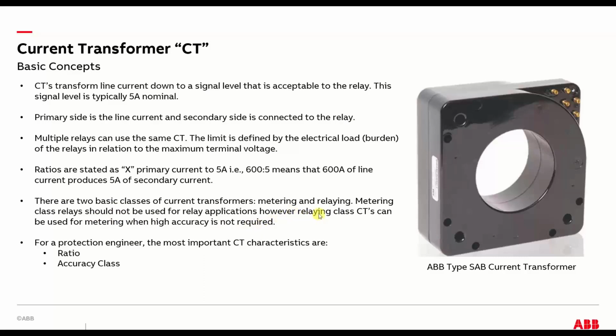They're not designed for that. They're designed to be accurate, but they're not designed to have a large range on them. So when you do a relaying application, you're going to select a relaying class CT. Now in the inverse, a relaying class CT can be used for metering, but you may have some reduction in accuracy. So kind of the bottom line, and I'm going to move off the CTs as fast as I can because this just gets too deep.